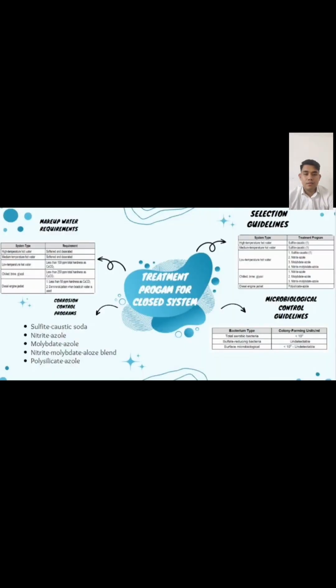The fourth mind map is the treatment program for closed systems. For makeup water requirements by system type: high temperature hot water is softened and dealkalized. Medium temperature hot water is softened and dealkalized too. Low temperature hot water is less than 100 ppm hardness as CaCO3. Chilled, brine, and glycol is less than 250 ppm total hardness as CaCO3. Diesel engine jacket, requirement number 1 is less than 50 ppm hardness. Second is demineralization when brackish water is used.